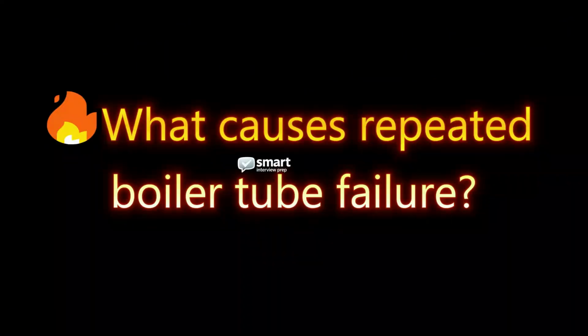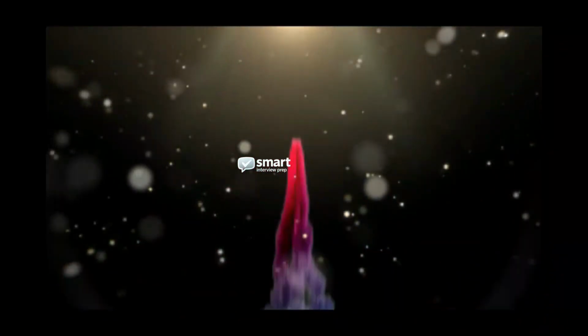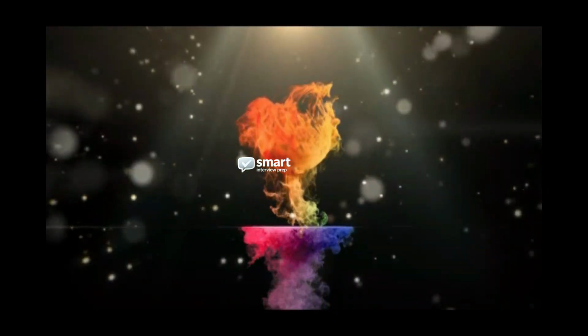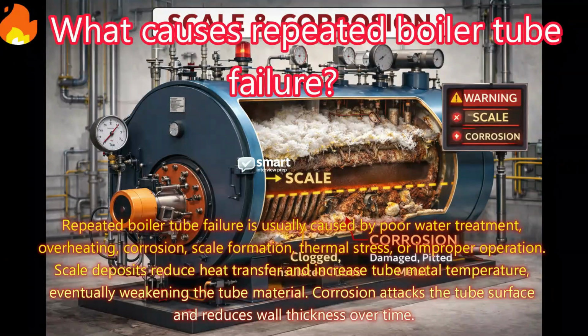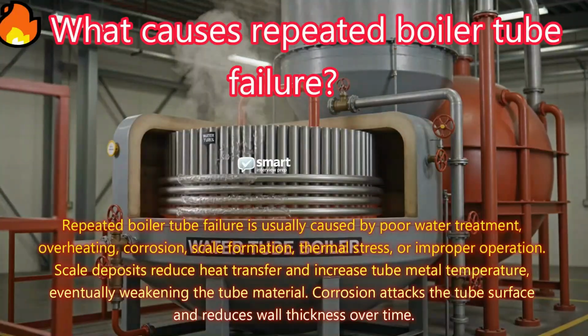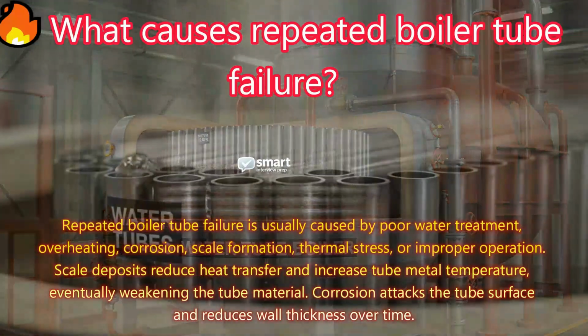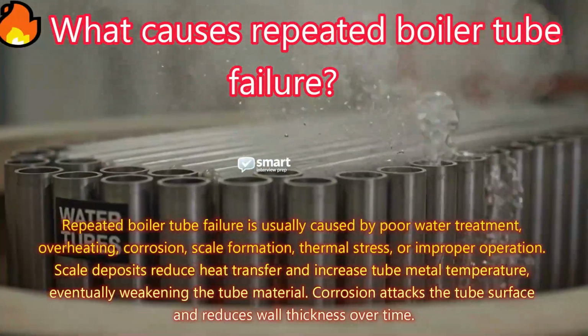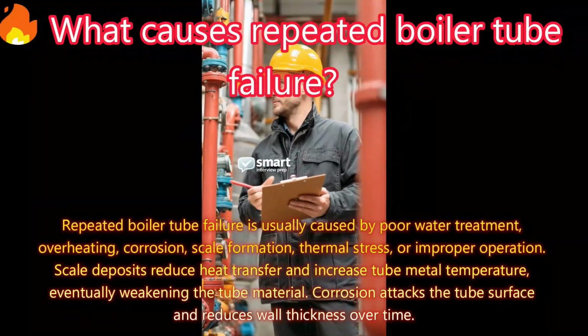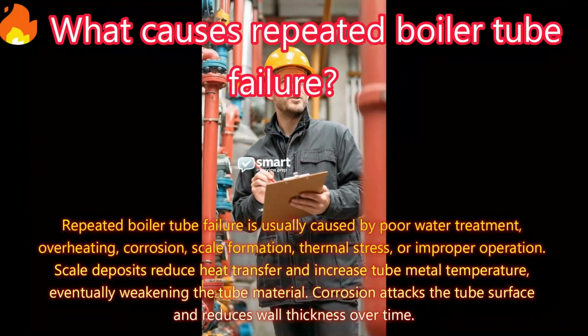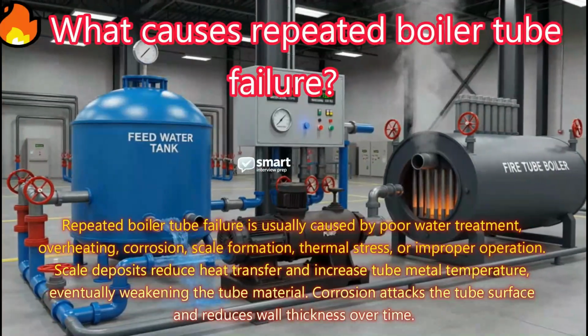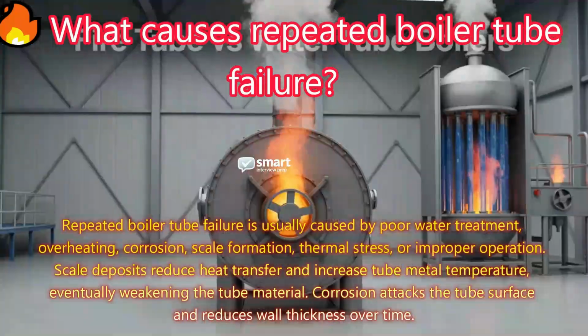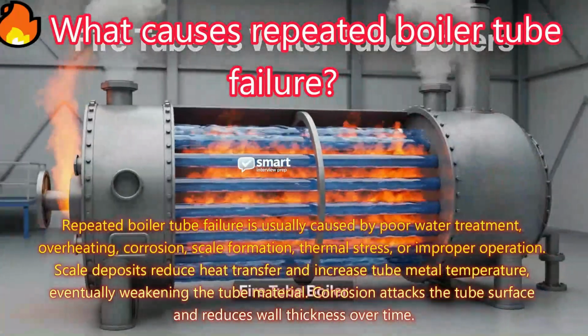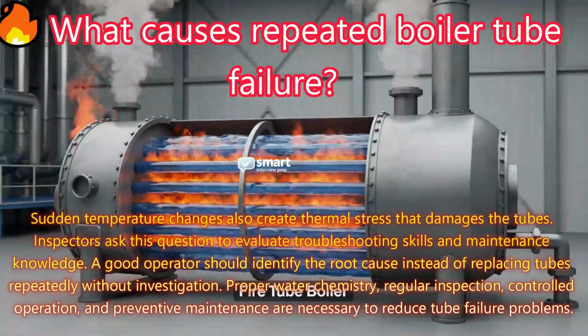What causes repeated boiler tube failure? Answer: repeated boiler tube failure is usually caused by poor water treatment, overheating, corrosion, scale formation, thermal stress, or improper operation. Scale deposits reduce heat transfer and increase tube metal temperature, eventually weakening the tube material. Corrosion attacks the tube surface and reduces wall thickness. Over time, sudden temperature changes also create thermal stress that damages the tubes.